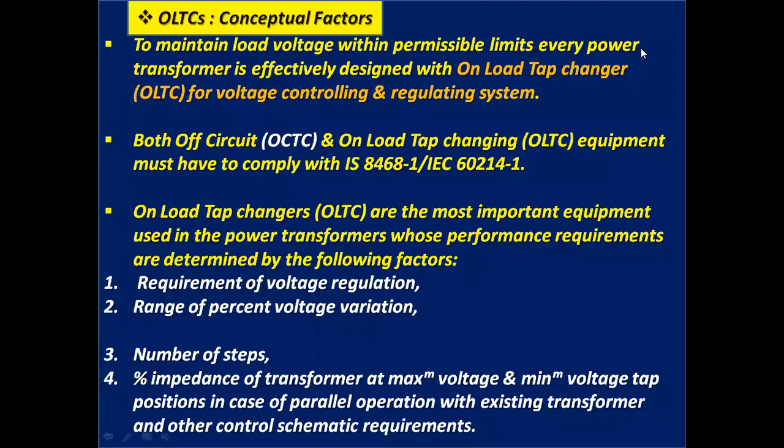Let's start with on-load tap changers, conceptual factors. To maintain load voltage within permissible limits, every power transformer is effectively designed with on-load tap changers for voltage controlling and regulating system.